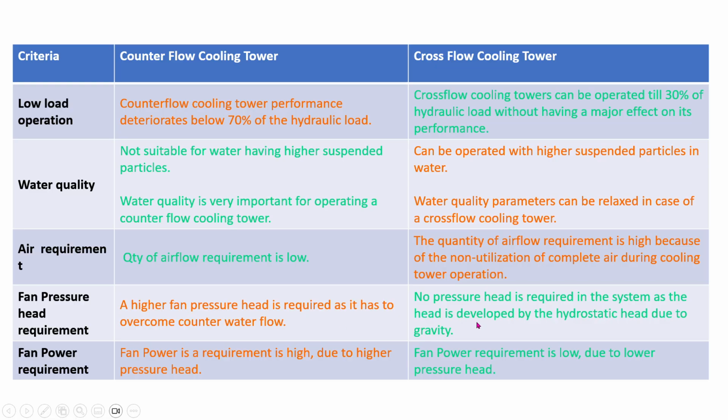Here, no pressure head is required in the system, as the head is developed by the hydrostatic head due to gravity, because here water is falling from the basin at the top, with gravity. So pressure will be less. So fan pressure is not required, particularly compared to counter flow, it is not so high.